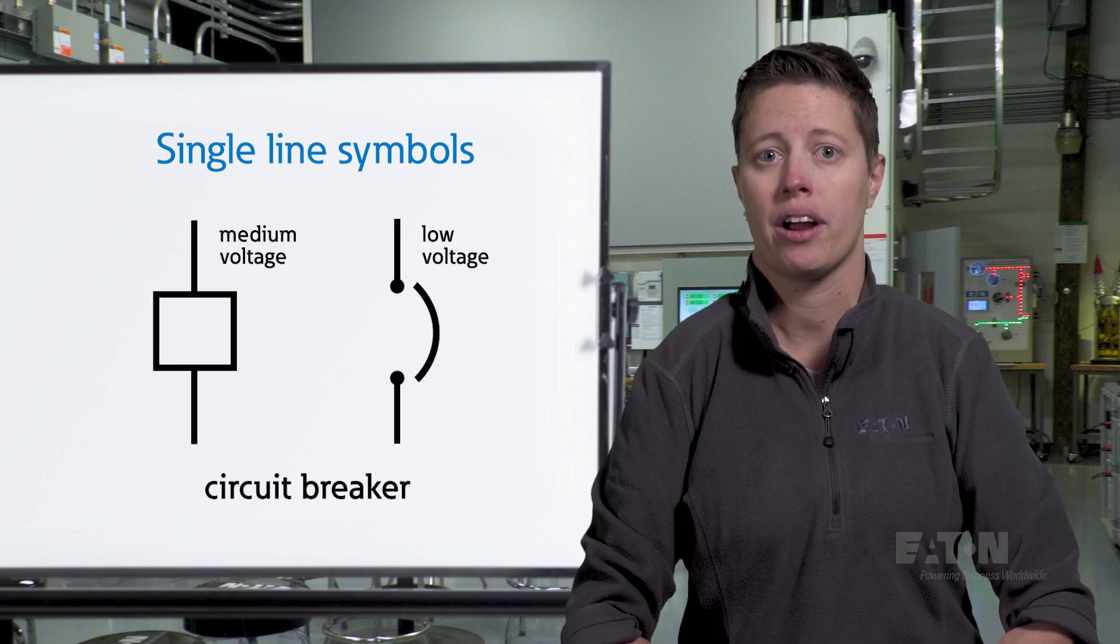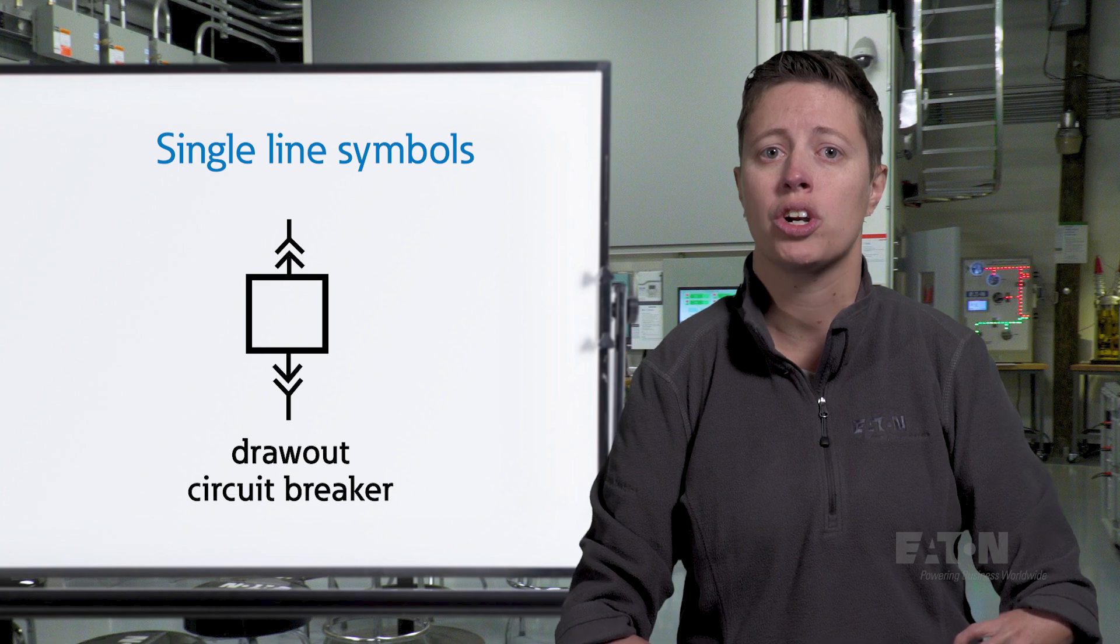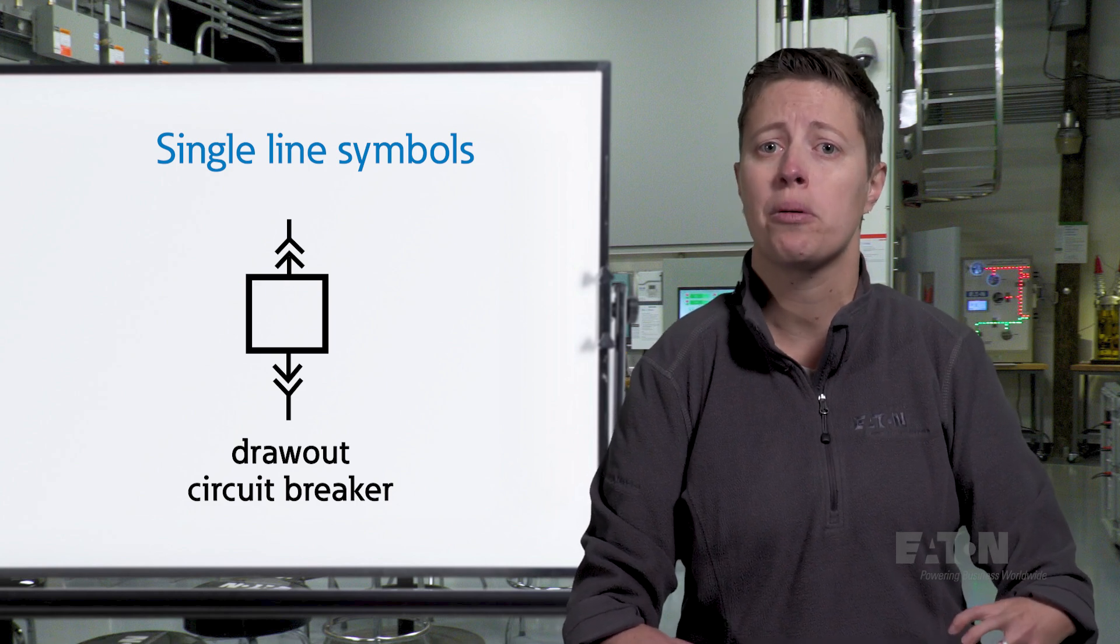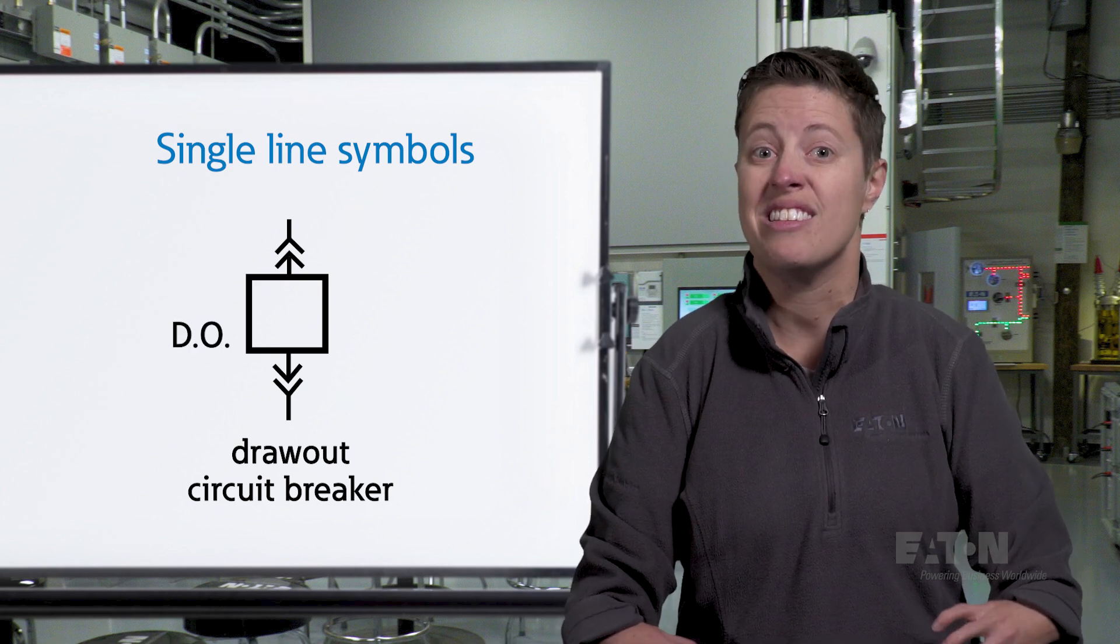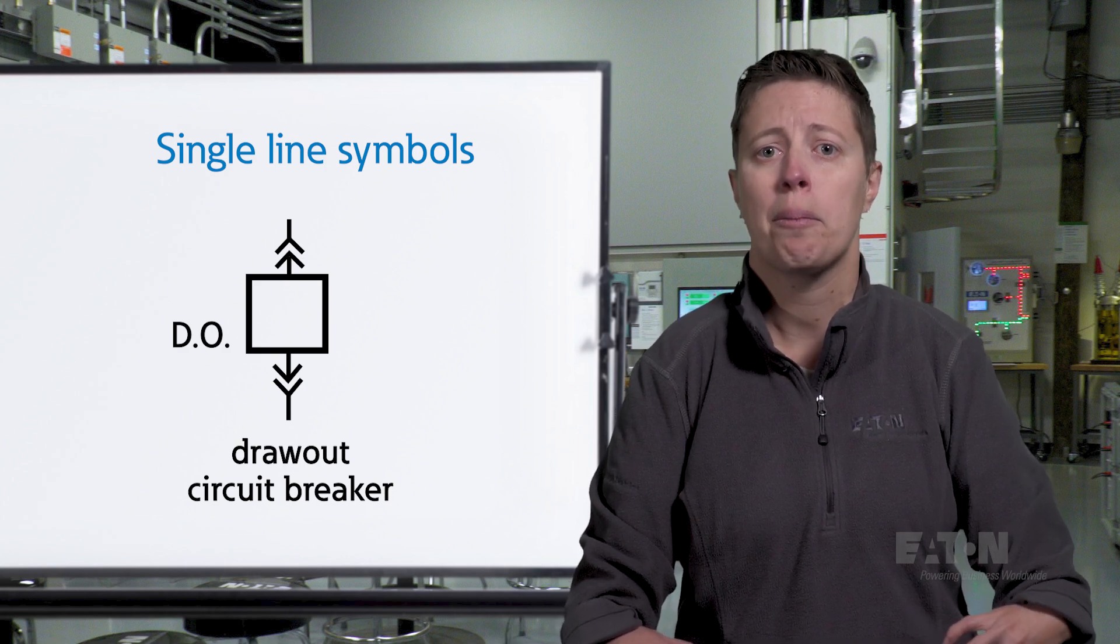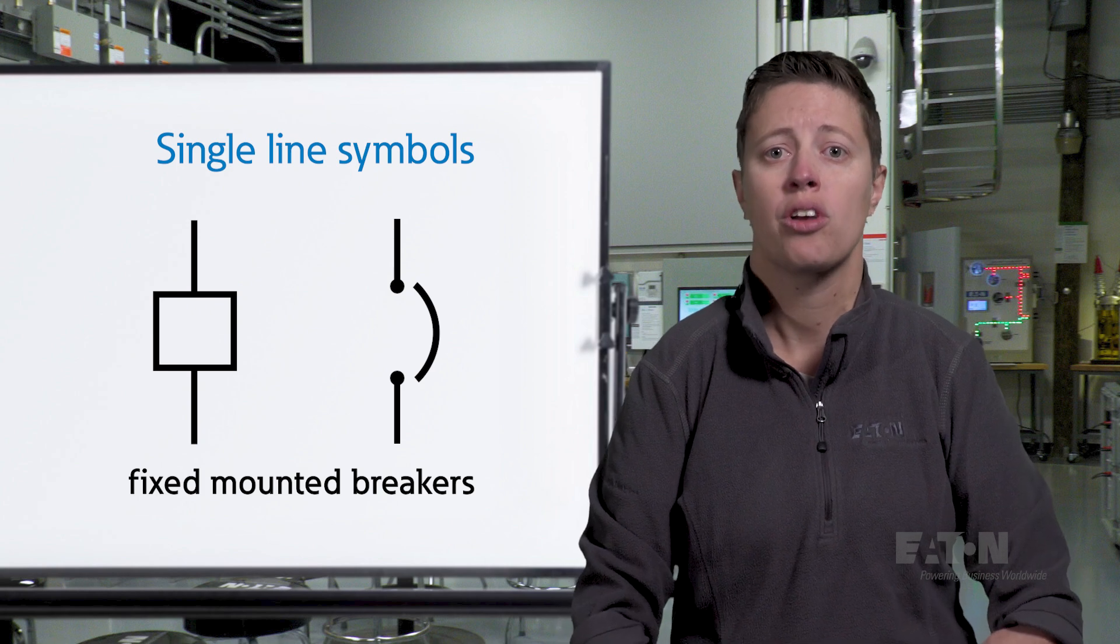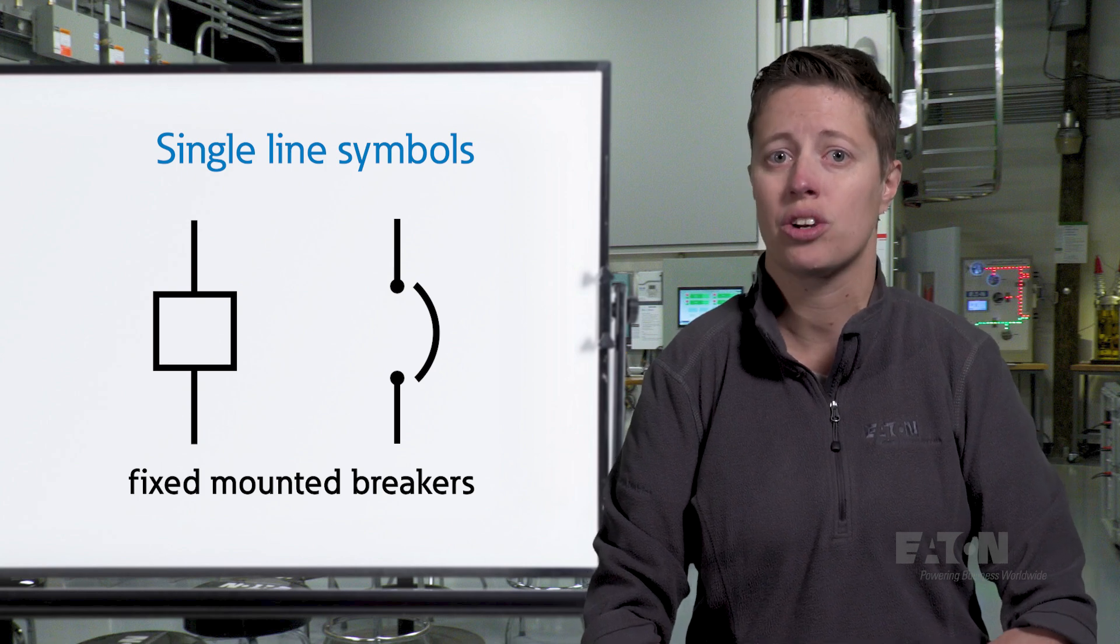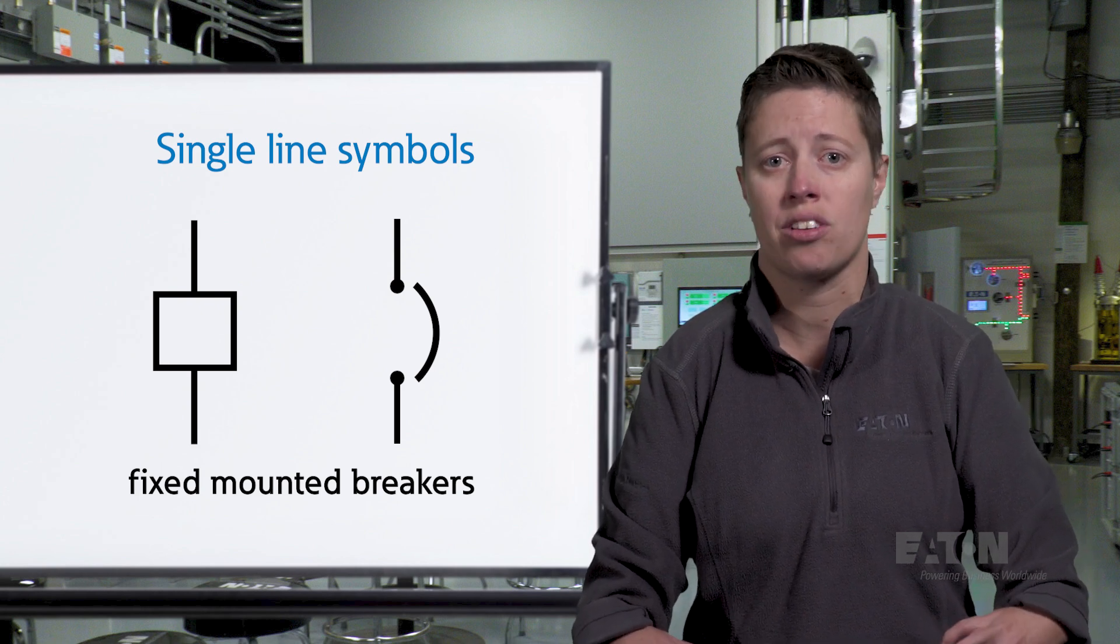A draw out circuit breaker symbol represents a breaker that can be removed from its enclosure for maintenance or replacement without disturbing the wiring of the equipment. Draw out capability is typically represented by two carets or chevrons above and below the circuit breaker. The abbreviation DO indicating draw out may also be noted. Draw out breakers are commonly used in applications where frequent maintenance or testing is required. On the other hand, fixed-mounted circuit breakers are permanently installed in their enclosure. Fixed-mounted breaker symbols do not include any additional carets or chevrons. Fixed-mounted breakers are used in applications where the breaker does not need to be frequently accessed for maintenance.